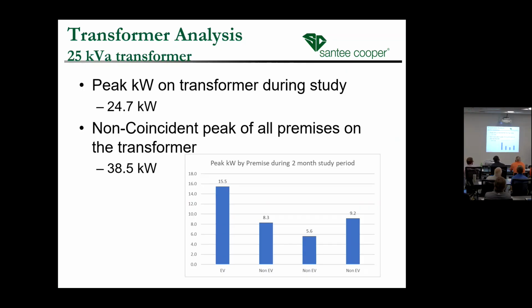This transformer specifically has one EV driver. This first bar here was the EV customer. This graph is showing their non-coincident peak on the transformer, so all of these folks were not on at the same time, but this was their peak for that 2-month study period. This EV had a 15.5 kW peak compared to 9.2 for the next highest customer. And I promise we didn't just pick this one because it had a higher peak—every customer we looked at on the EV system was similar, where the EV customer was pretty much the highest, except in one case where there may have been one or two folks higher than that EV customer.